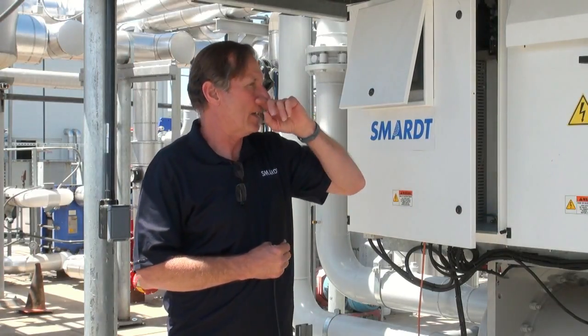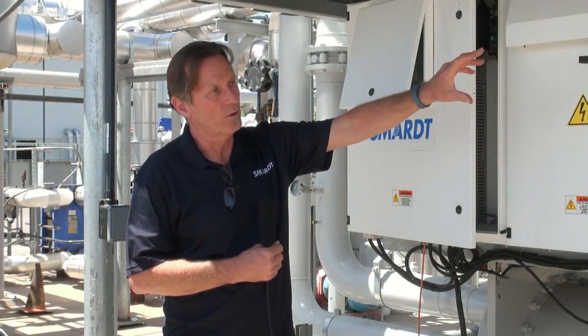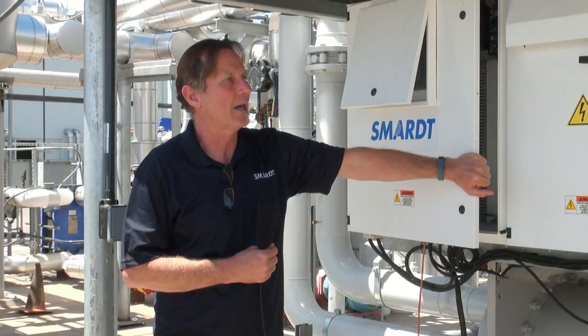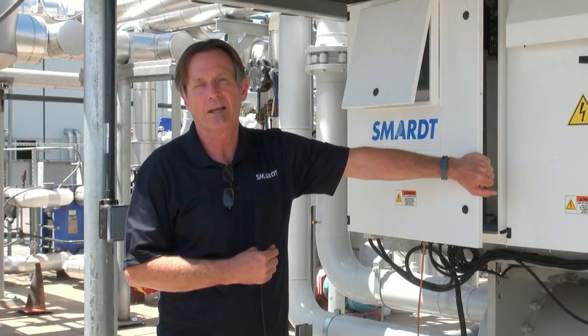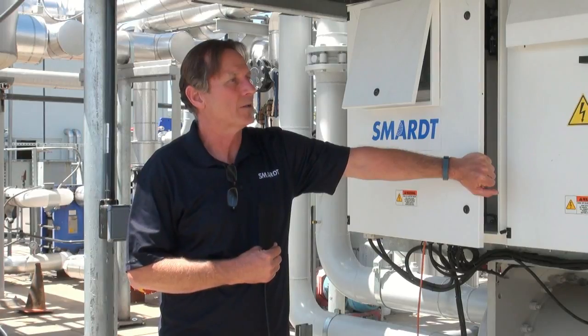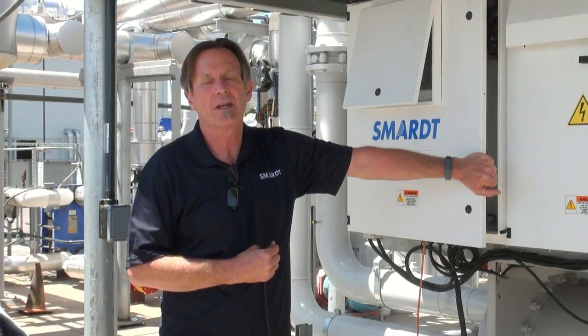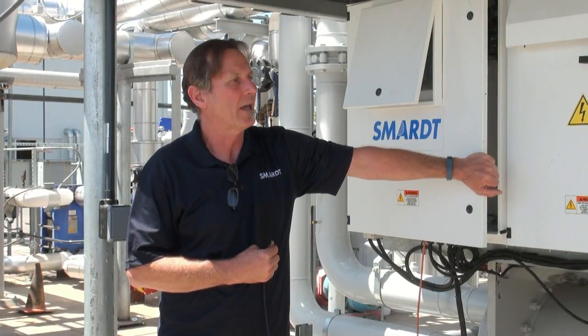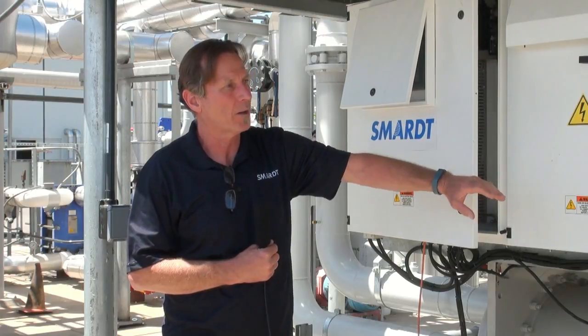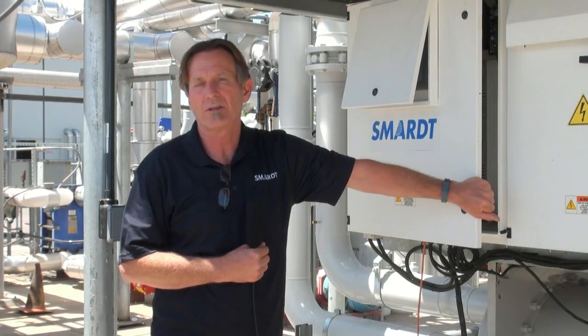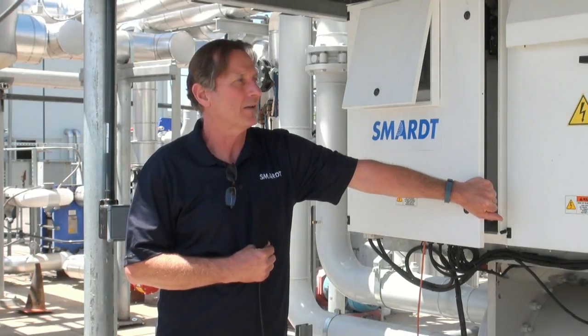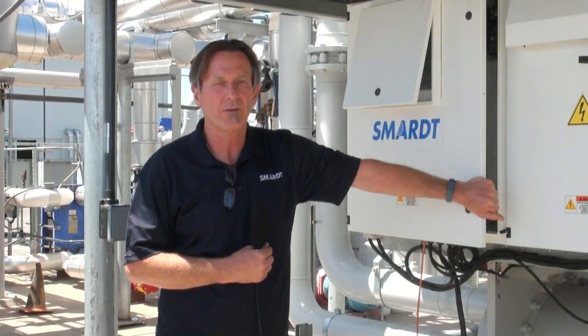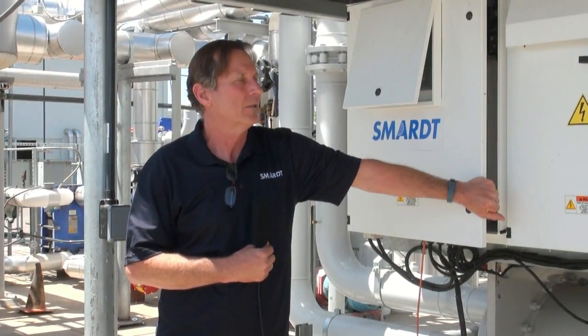In the cabinet, there's not a lot in there. We could open up the cabinet a little later and show you, but you've got the power coming in to the disconnect switch, and then you have a line reactor in the bottom of the panel, which is downstream of the disconnect switch, and that then has a feed to each compressor.